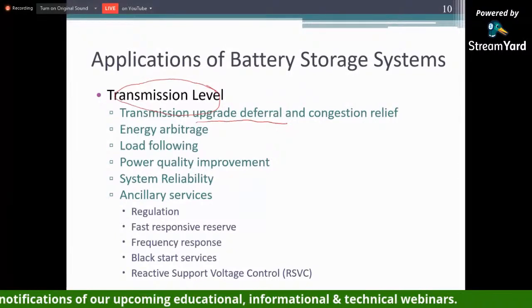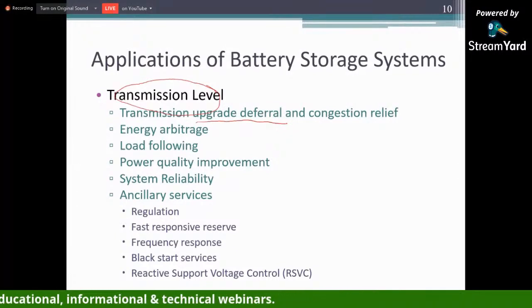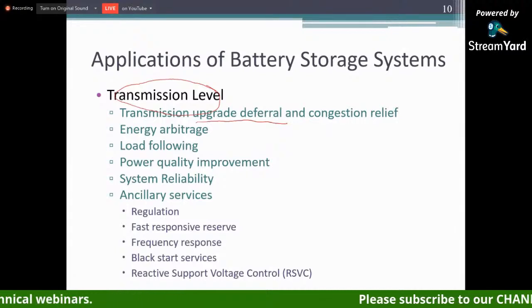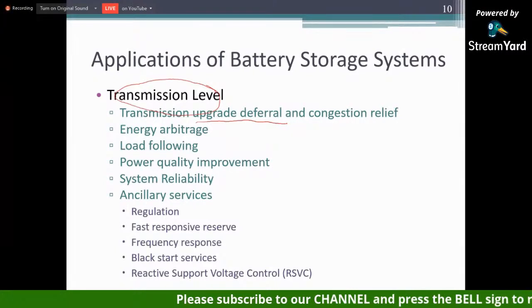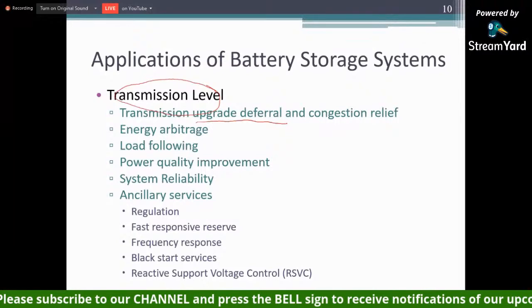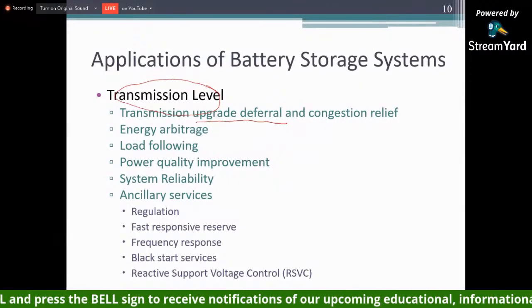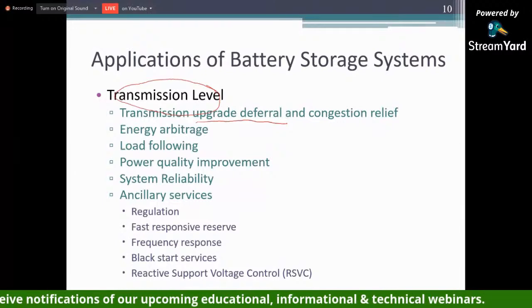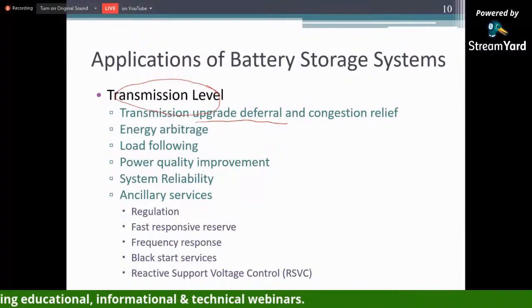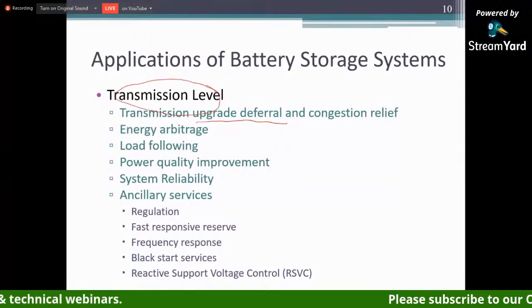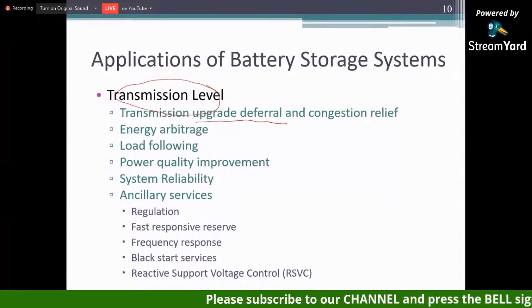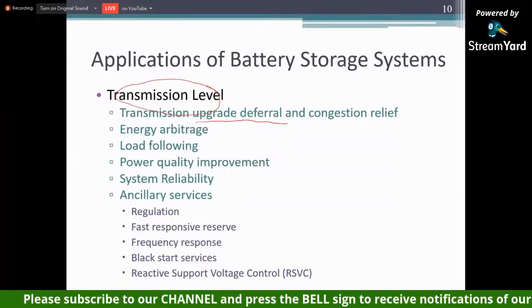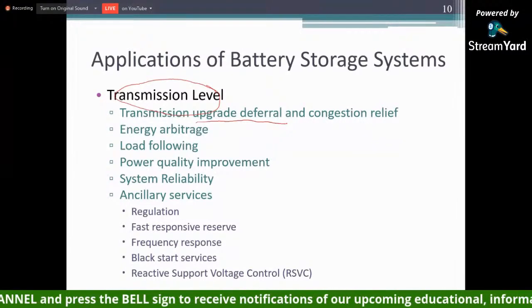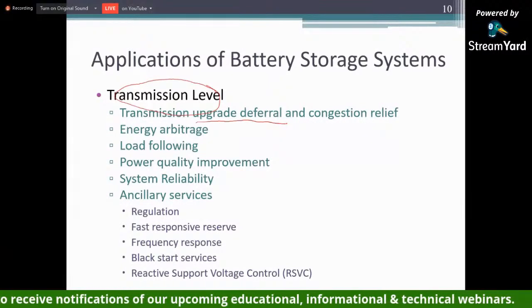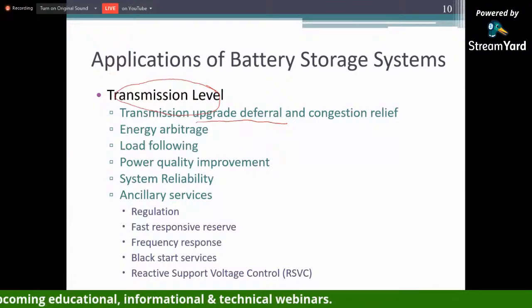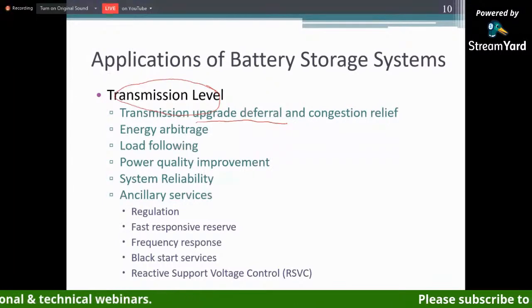When we do transmission planning or transmission construction, we always try to meet the need at the peak. So the simplest approach is to use storage to do peak shaving, dropping the peak loading on the transmission line and shifting it to the off-peak period, then transferring the energy to the location near the load center before you use it. Then you'll be able to do construction deferral or congestion relief.